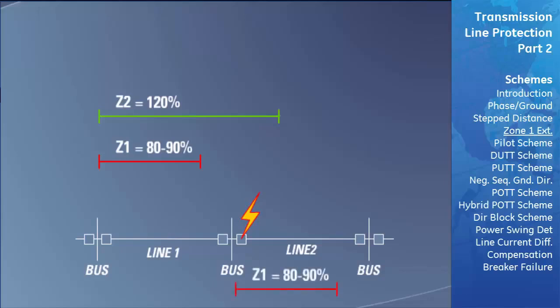The disadvantage of the Zone 1 Extension Scheme is that external faults within the extended Zone 1 reach will trip the breaker instantaneously, even if that breaker did not need to be tripped. This needless tripping increases the amount of breaker maintenance needed and causes a needless loss of power supply to some customers.